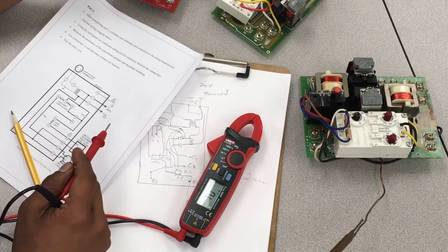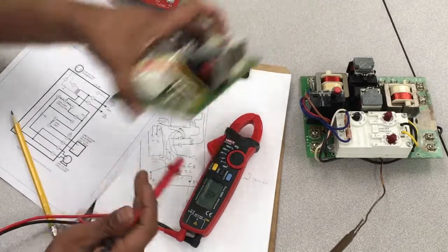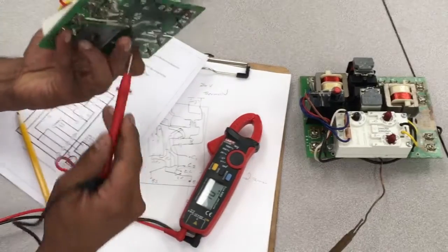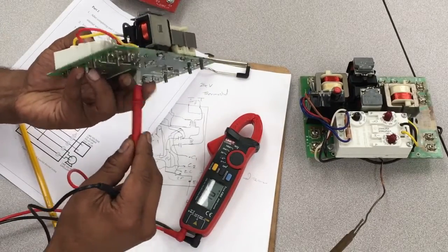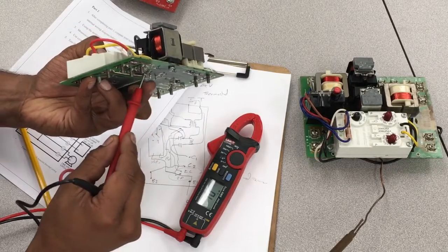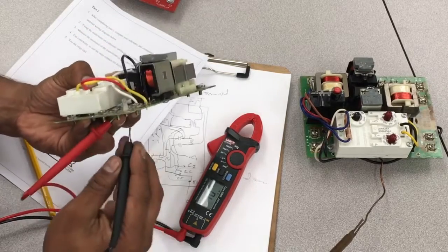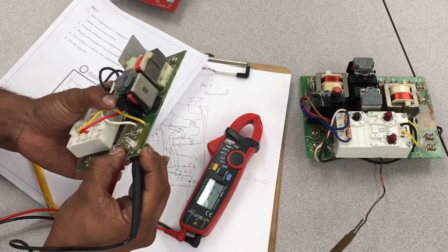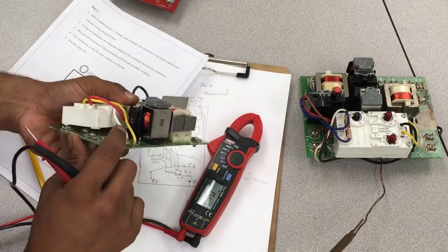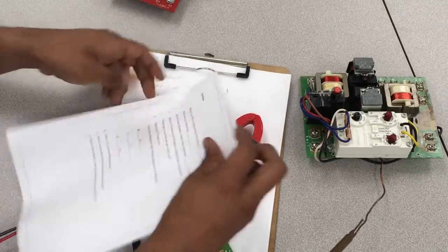Use continuity test the relay for function. So how do we test those relays? We test the coil continuity, and you can test those little connections in here and see if they are continuous or not. If I put 2 leads in those settings and I press with my finger here, these should connect. You can have a colleague help you do that to test that these contacts are actually making the proper connection. And that's about it to answer the questions.